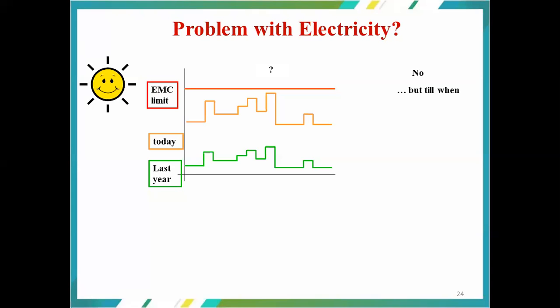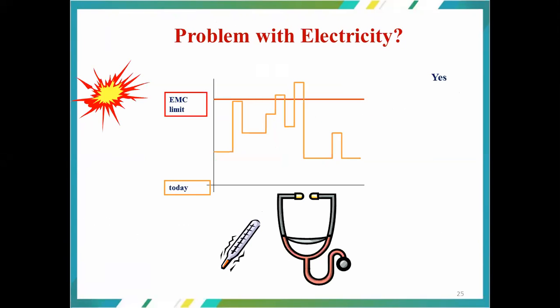When it comes to the EMC limit, all the utilities as well as the equipment are going to have an EMC limit. If it is within the prescribed limit, there won't be any issues. That means the device or equipment is going to operate safely and provide the required results. If in future it exceeds the set value, then we are supposed to go for remedial measures. There come the filters, or you can have active power conditioners or passive power conditioners, and we are supposed to bring the value down to less than that set by the standards for the EMC.